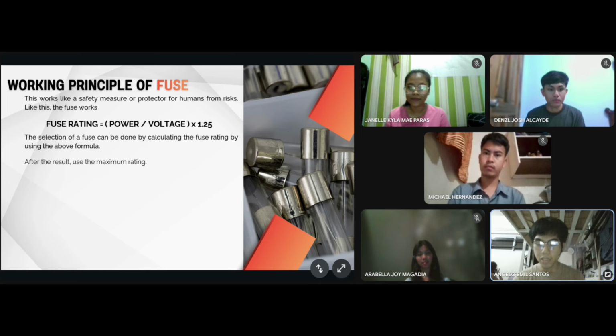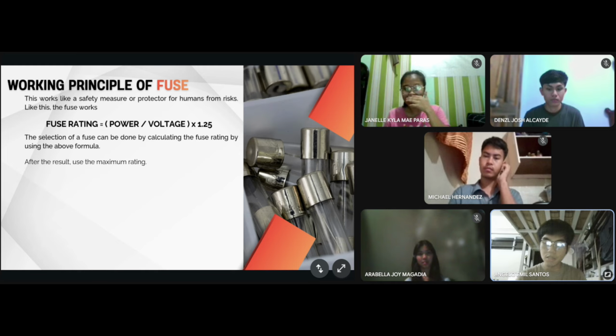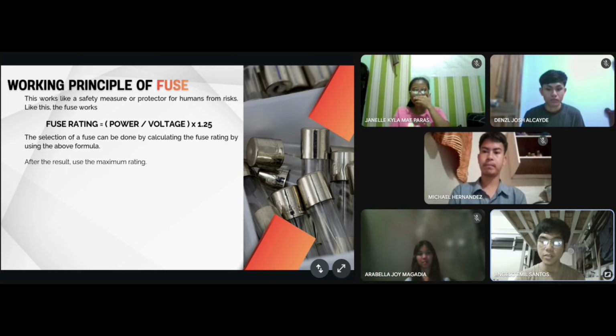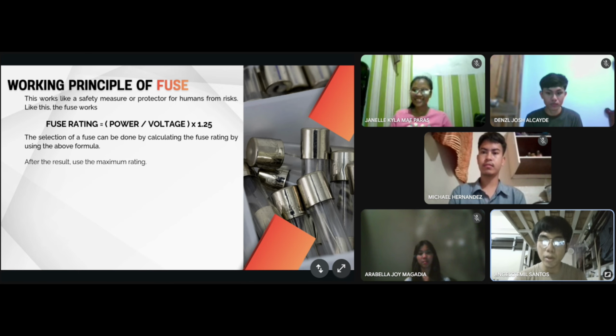Ang formula na nakikita nyo is kung paano ba mag-compute ng fuse rating. And always remember na ang unit nito ay in amperes. So, for example, may 500 watts ka na electric kettle and connected siya sa 50 volts outlet. Divide lang natin yung 500 watts sa 50 volts, then multiply natin sa safety factor na 1.25. Then, yon ang fuse rating na gagamitin. Also, take note na maximum fuse rating dapat ang gagamitin after makompute ito. For example, ang lumabas na value ng fuse ay 7.4, 7.5, or 7.6. Ang gagamitin dapat nating fuse ay 8 ampere.